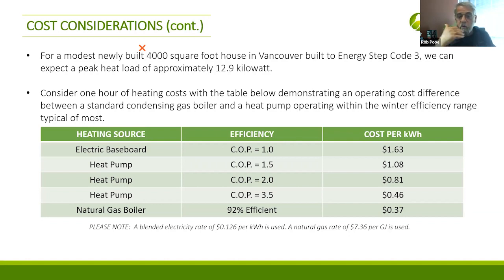If you get a heat pump with an efficiency of 1.5, on the lower end, your operating cost for that hour is $1.08, and so on. When we get to a heat pump with a COP of 3.5, those are your high-end heat pumps—not extremely exclusive, they exist on the market, but they're the higher end, cold climate ones, for example. Look at the cost there: it's 46 cents for that same hour. And if you took a 92% efficient gas boiler, it would be 37 cents.